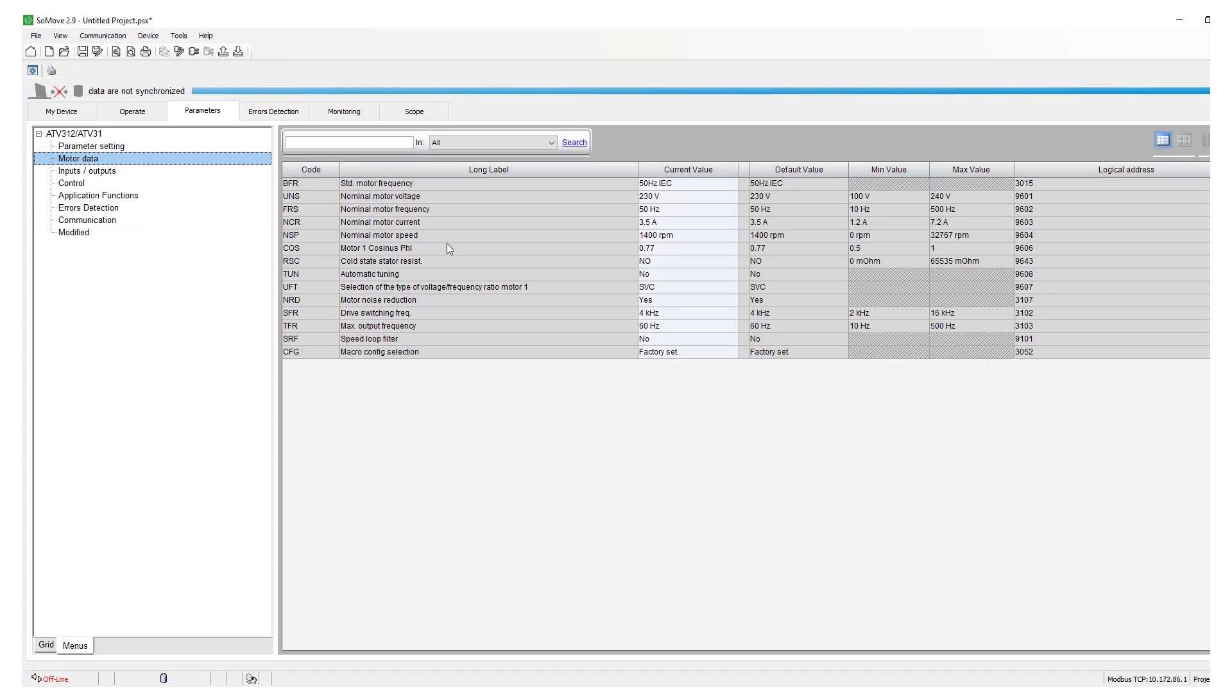Make sure all your motor parameters such as standard motor frequency, voltage, current, speed and cosine are set for the motor nameplate. Also you need to check UFT which is motor control parameter.